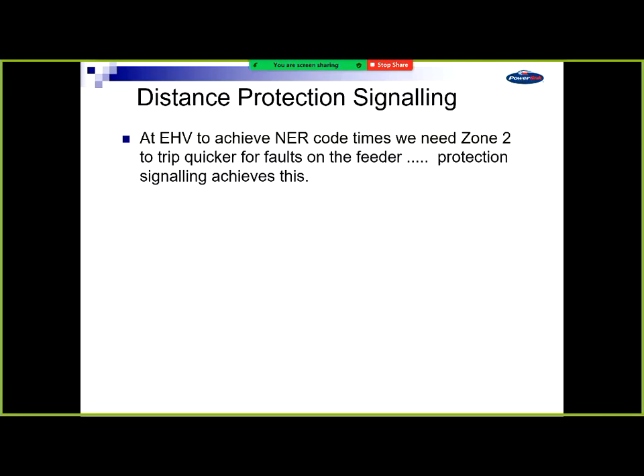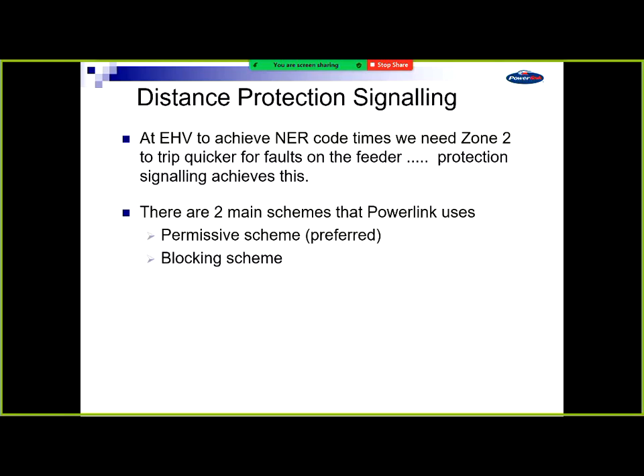So for the transmission network to achieve those code times and discrimination, as I said, you need signalling to get 120 milliseconds. If your feeder on a sub going out is to clear in 100 milliseconds, you've got to clear in 120, but you've got to say it's on my feeder, and not 15, 20 or 30 metres over onto the next feeder, and our feeder is 100 kilometres long. 30 metres in that is just errors. That's 0.03%. You can't distinguish between a fault on the end of your feeder and the start of another feeder. And you've only got 20 milliseconds less to trip faster. You've only allowed 20 more milliseconds in time in the code. You can't discriminate because 40 milliseconds of that time has to be your circuit breaker. So you've already sent out a trip signal when his breaker's opened.